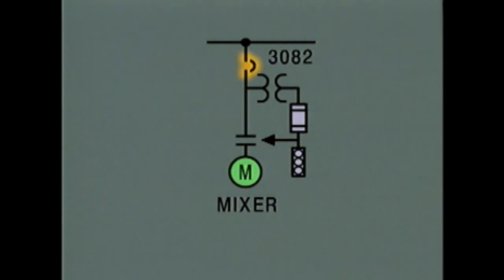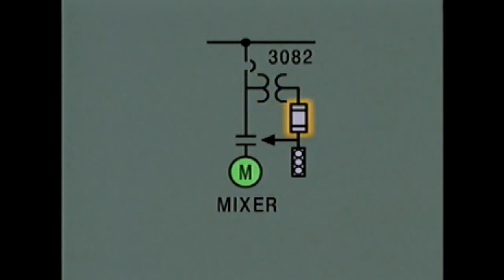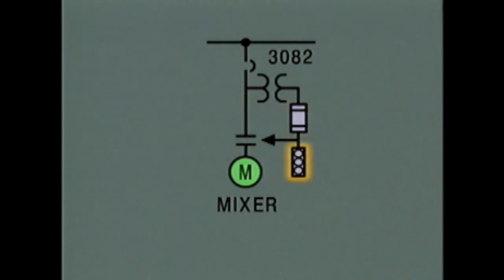In the power circuit, power passes through a circuit breaker and a contactor to the mixer motor. In the control circuit, three components are shown. A potential transformer reduces voltage. A fuse interrupts the flow of power in the circuit if the current in the control circuit gets too high. And a start-stop switch is used to operate the motor.